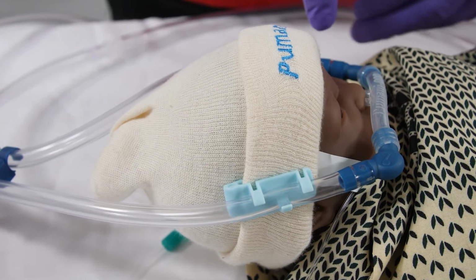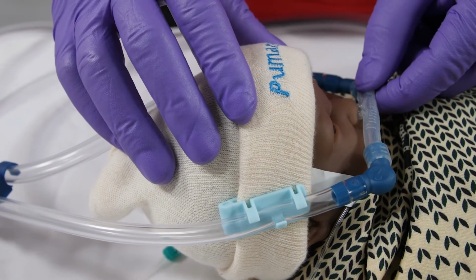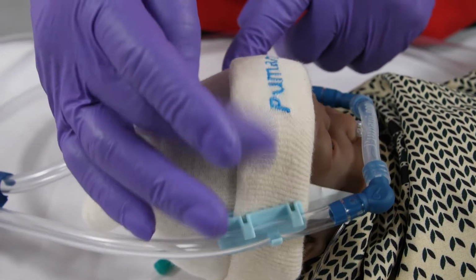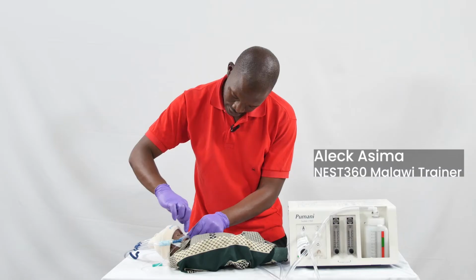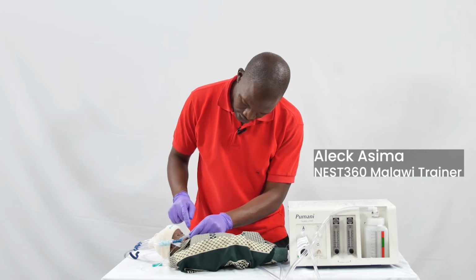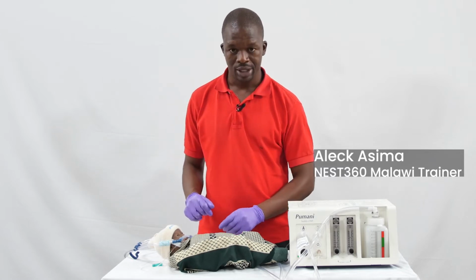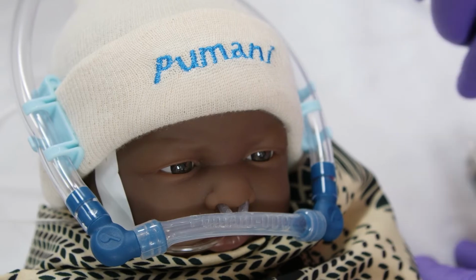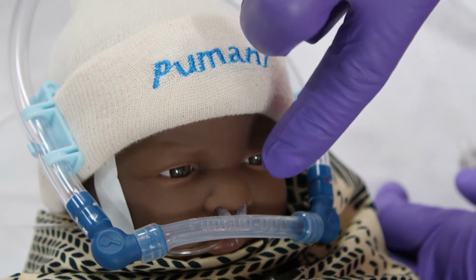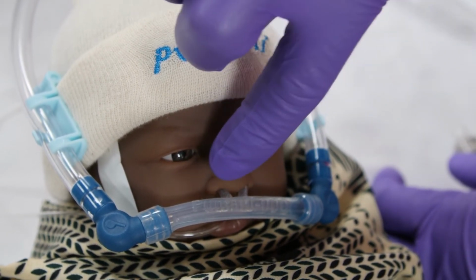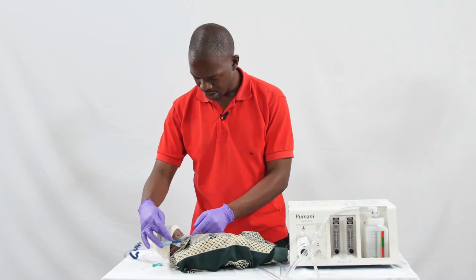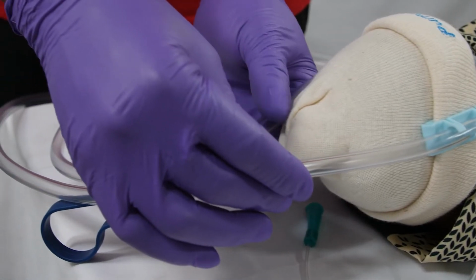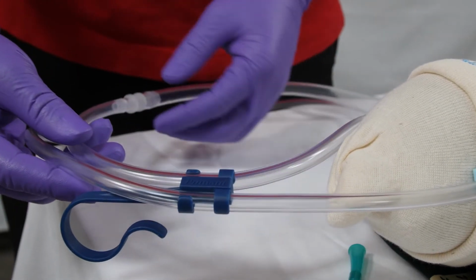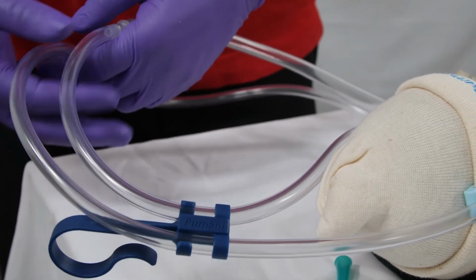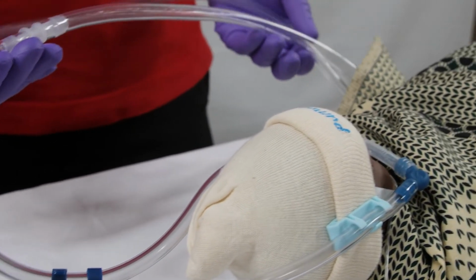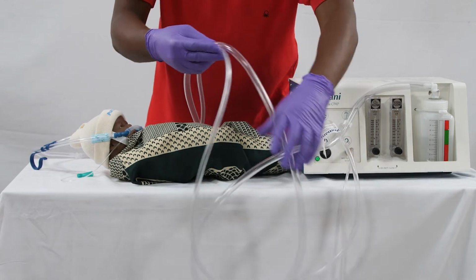First, check the prongs are in place and that the hat is on properly. Also, make sure you are still able to see the lines on the nasal prongs. After 1 or 2 days, some prongs may be loosely fitting, so you may need to change the prongs, but in our case, the prongs are still tightly fitting. Make sure the prongs are well adjusted on the hat clips and tube clip. Run through the length of the connecting tubings to make sure that they are not kinked anywhere.